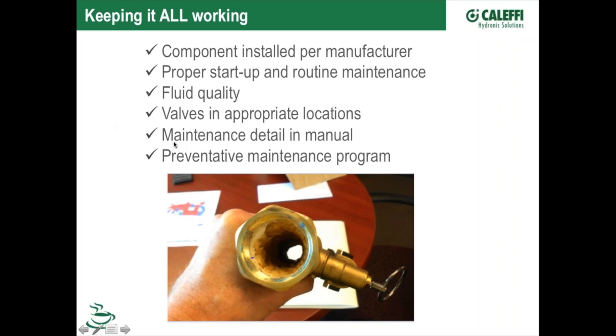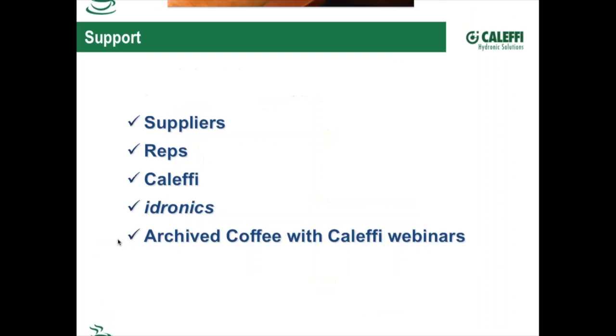Explain that to your customer, to the homeowner, to the building owner, what's required to maintain a valve. If you've got valves in domestic water systems, if you've got hard water, they're going to have to go in there occasionally and descale that valve. Thermostatic mixing valve is a classic example of that. You know, help them put together a program. Say, I'll come back every 6 months, I'll check your valves, make sure that everything's working properly. So just don't assume that it's in there and it just stays there forever. It's going to work fine.